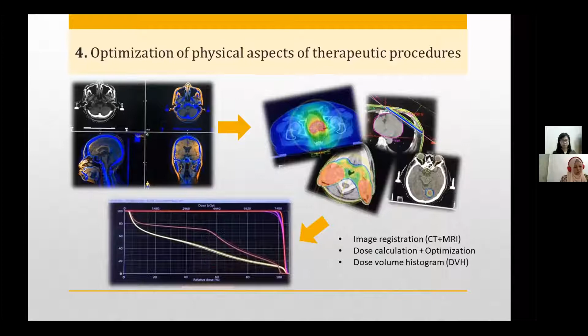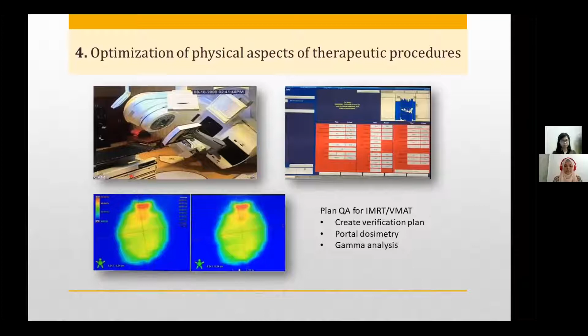This is an example for plan QA for IMRT or VMAT. We create a verification plan first, and then we capture the dose delivered by the treatment machine, and then perform gamma analysis.